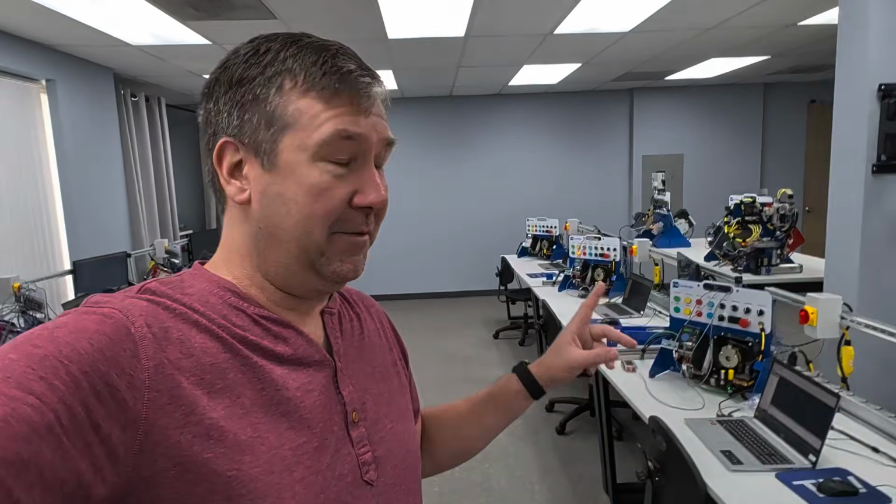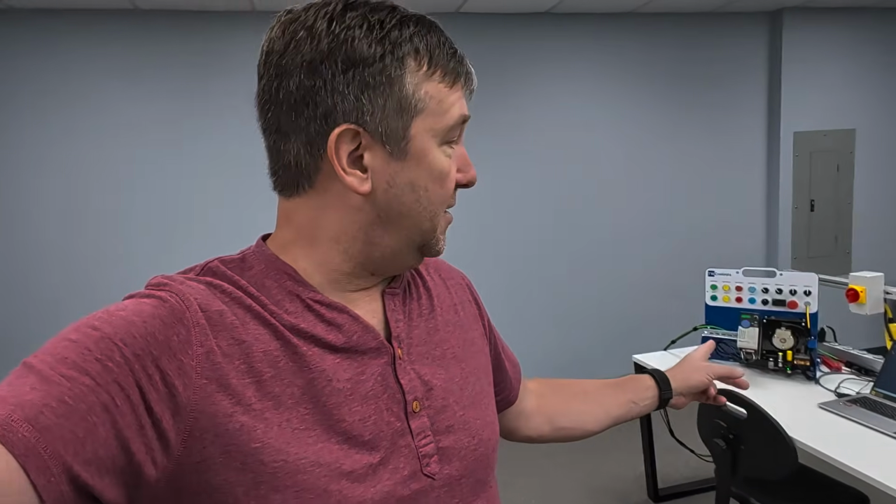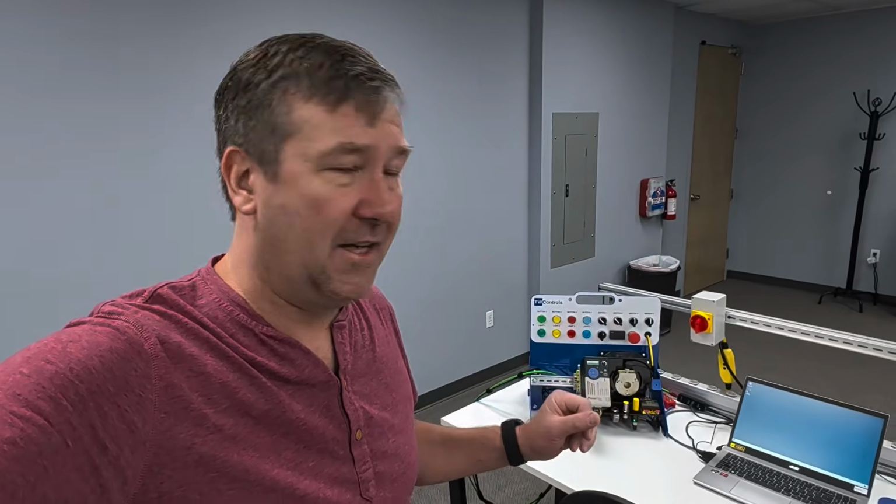Somehow I started flooding the network with enough packets that I believe, or at least that's what I think, the PowerFlexes started dropping offline. Now in the end, what I was doing was, Michael was working down here on station 1. We're making some upgrades, taking it to the latest version of Studio 5000 and the latest version of TIA Portal. Once a year, we upgrade all the images. So he was working on this, and he needed one big file. Usually we copy them over hard drives, but I just went into File Explorer and started copying that file.